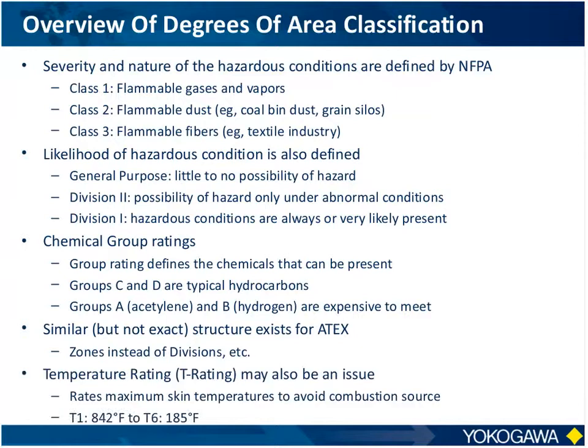Finally, you have what's called a T rating, which deals not with an arc or spark, but with heat. For example, if you had a heater or motor that gets hot, how hot can that temperature get before it acts as an ignition source? You'll hear T ratings like T1 through T6, and depending on the chemicals present, that restricts how hot the items can be.